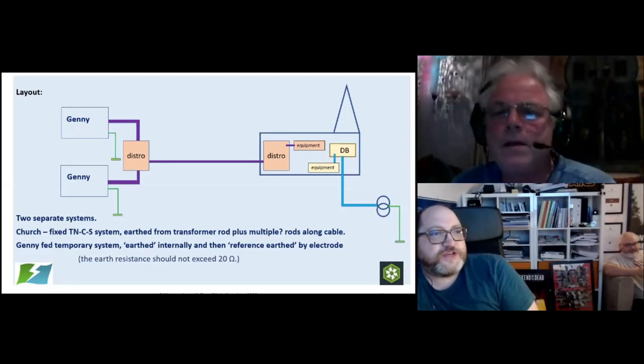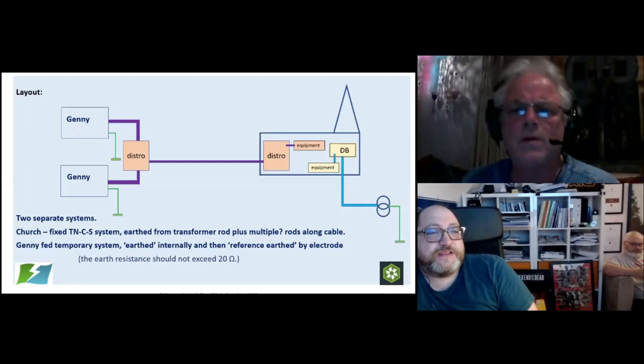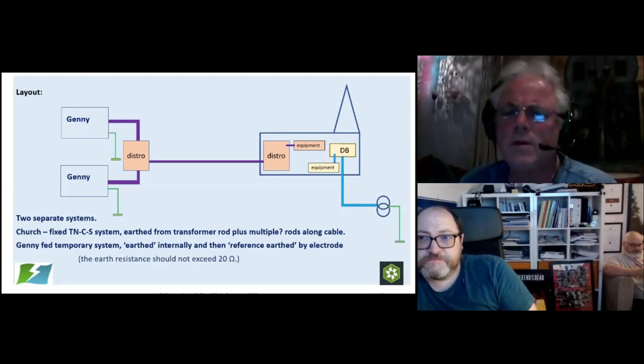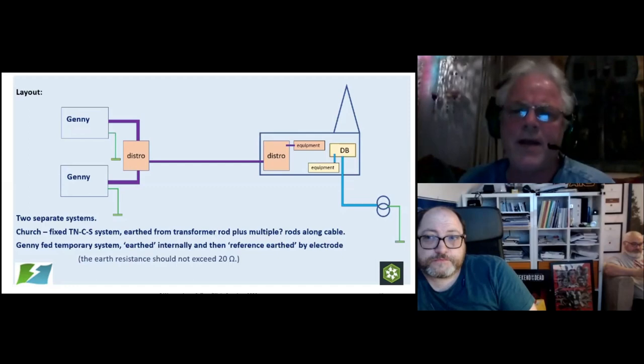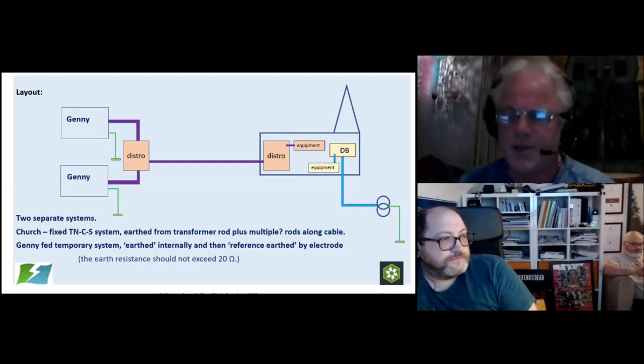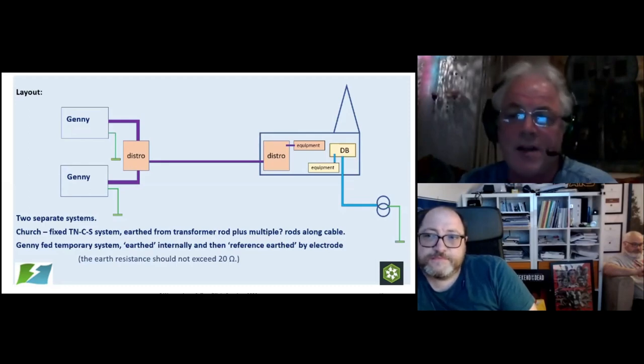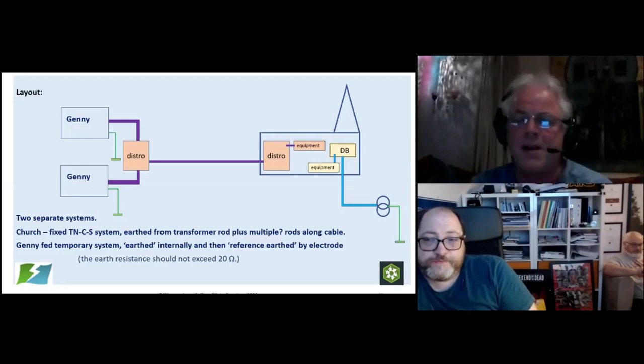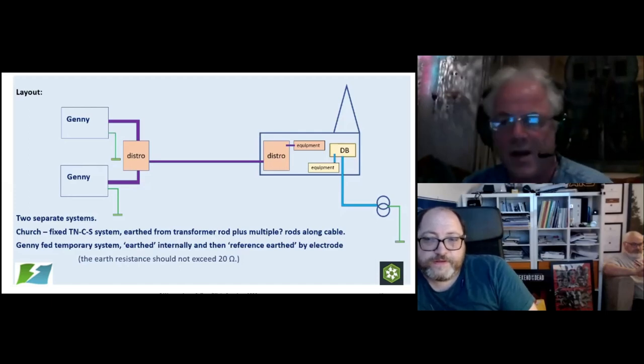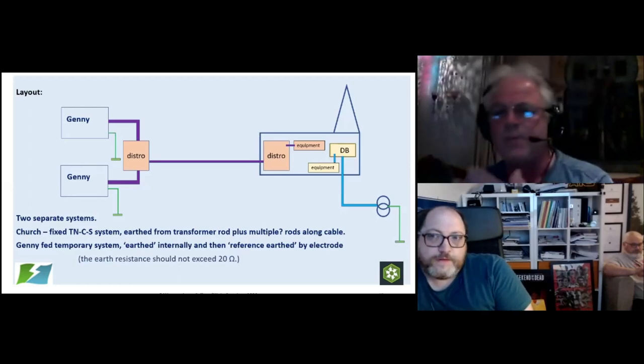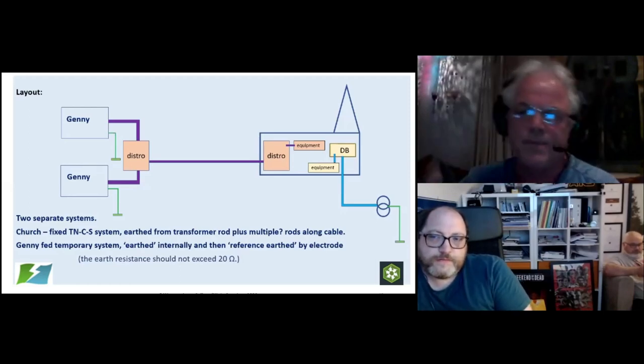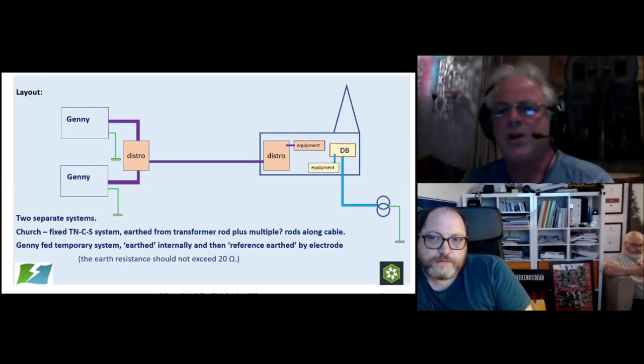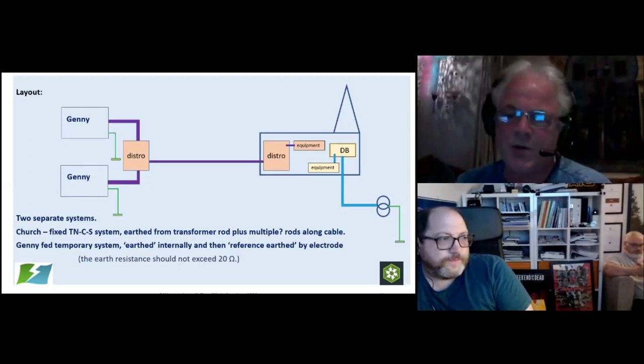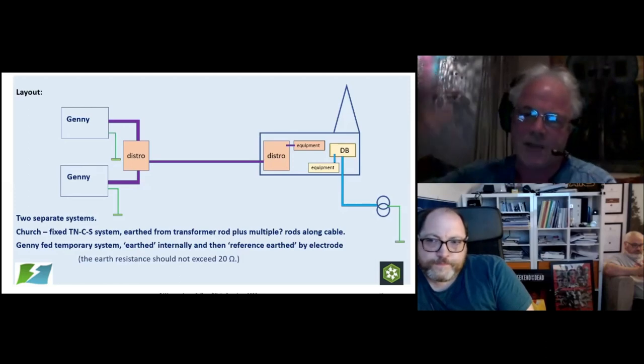David Crowley says, during the design using generators, do you need to apply a standard derating of 0.8? Well, there are a number of things we need to consider. Generators don't like running at 100%, and they don't like running at less than 30%. You don't want to underrun them. If they run at less than 30%, they tend to coke up, because they're not running at sufficient speed to burn all the carbon off. So they need to be running between 40, 50, 60, up to 70%. If you run at over 80%, it puts too much stress on them. So we try to run generators somewhere in the middle there.